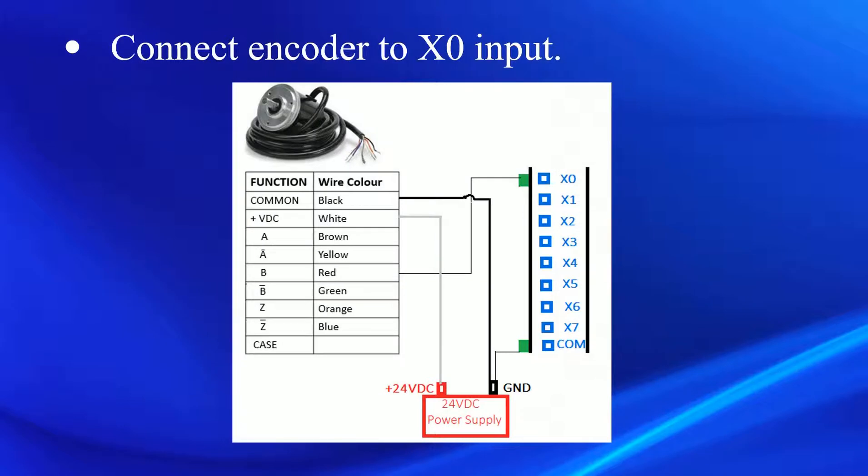In this setup, let's connect the encoder as shown in the schematic. The encoder is powered up using a 24 volt DC supply, and the pulse output of the encoder is connected to the input X0 of the FL4 module.